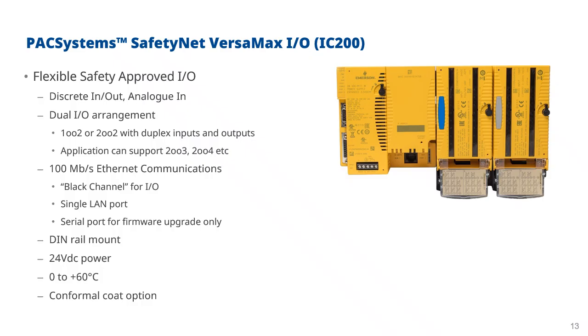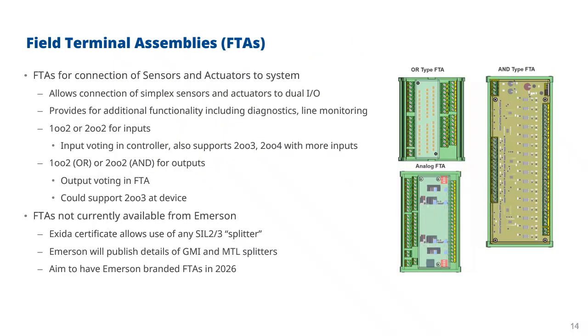To handle the dual I/O arrangement, what we will be using is what we call field terminal assemblies, or FTAs. These are also known as splitters. That's what the certifying agency calls them. But the idea of the FTA is to allow the connection of the sensors and the actuators to the system. Now, in many safety systems for SIL 2, there would only be a simplex sensor and a simplex actuator.